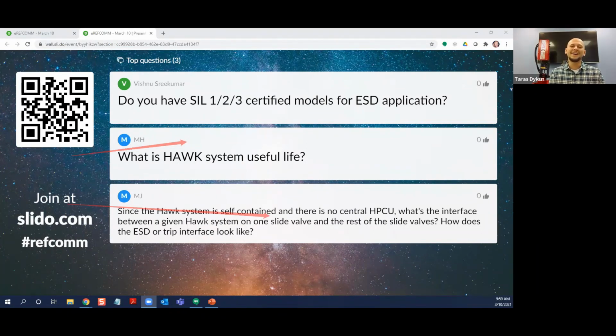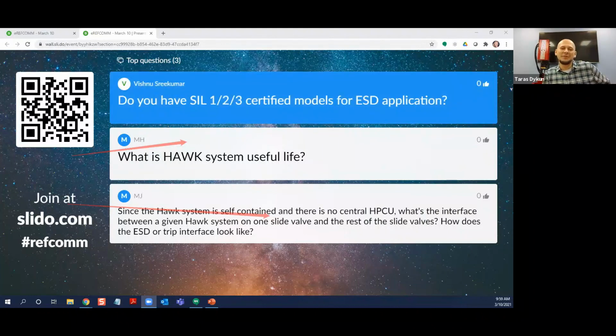So next question, do you have SIL 1, 2, 3 certified models for ESD applications? This is actually one of the things that we run into quite often. Usually we utilize SIL 2, or actually SIL 3 solenoid valves if required. And at this time, we are going through calculations to certify our ESD system to SIL 3, or SIL 2, or SIL 1, whatever we can get. Right now we're working on it.